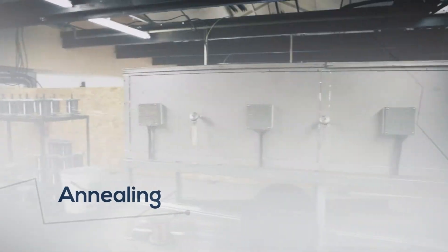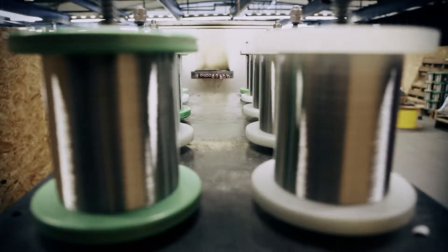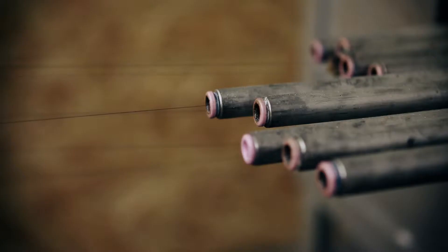During the wire drawing process, the wire becomes work hardened. This alters the physical and electrical properties of the wire, making it both brittle as well as moving the EMF reading beyond usable tolerance.